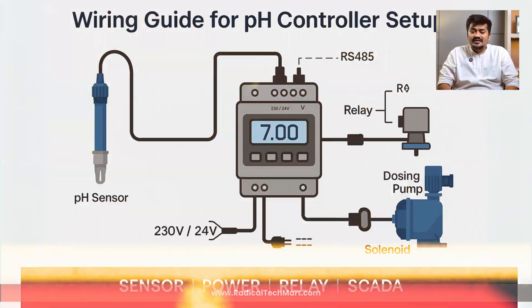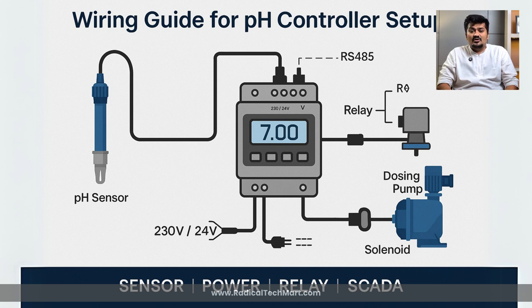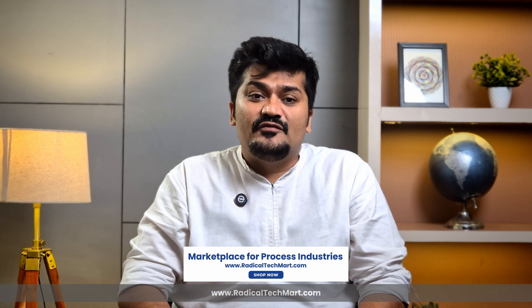Now let's cover wiring, installation and integration. Wiring a pH controller typically involves: sensor input via direct electrode or transmitter output; relay output to a dosing pump or solenoid valve; power supply, usually 230V AC or 24V DC; and an optional communication port if you want SCADA or BMS logging. Some controllers also offer dual control channels for acid and alkaline dosing from a single unit. Always ensure proper grounding and cable shielding for stable readings.